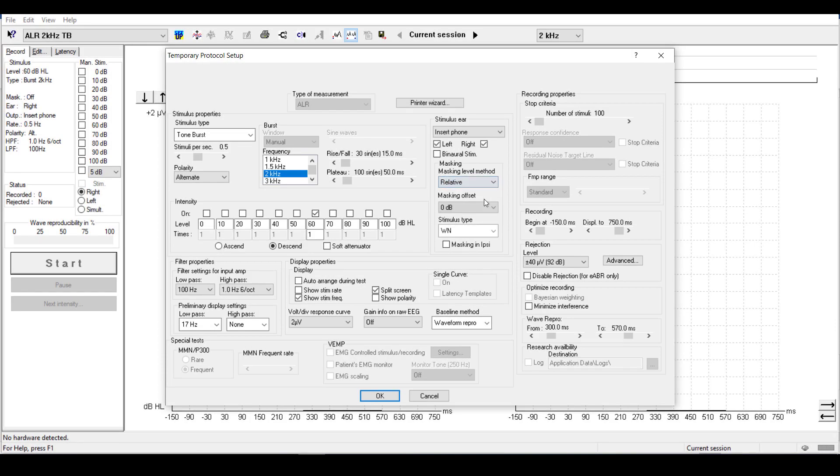The offset is the dB noise level relative to the stimulus level. If you increase your stimulus level, the offset remains the same, but the result value will vary. On the Eclipse, it is possible to use either of these values by entering them in the temporary test setup protocol.